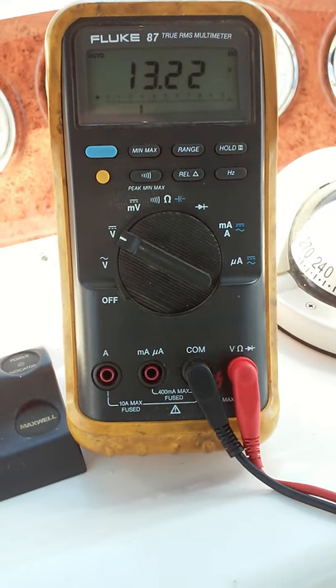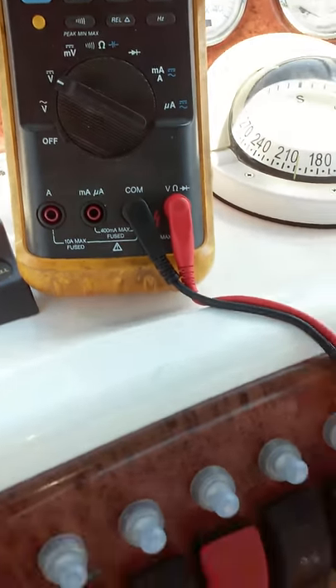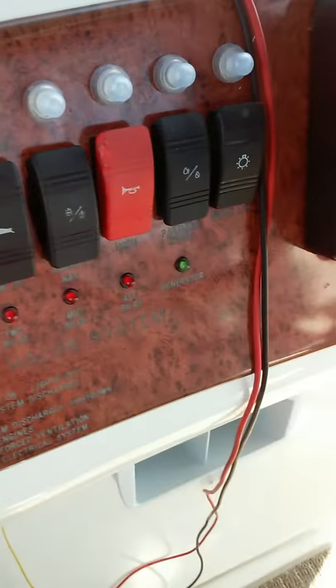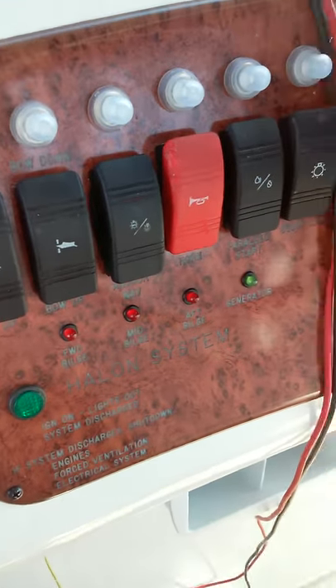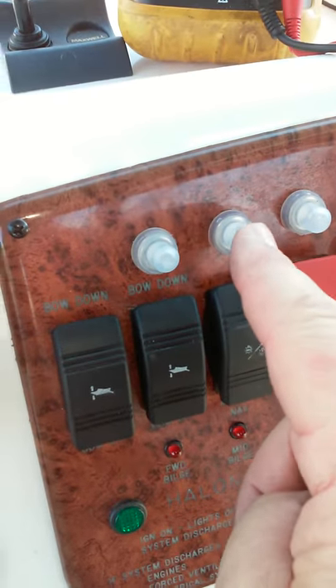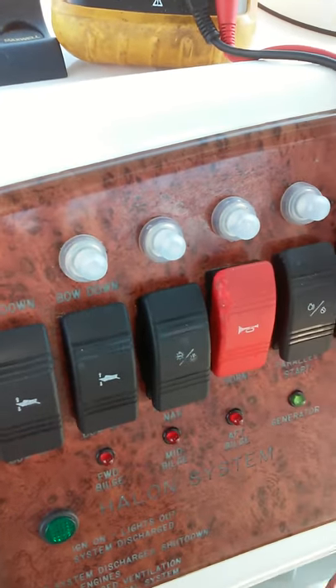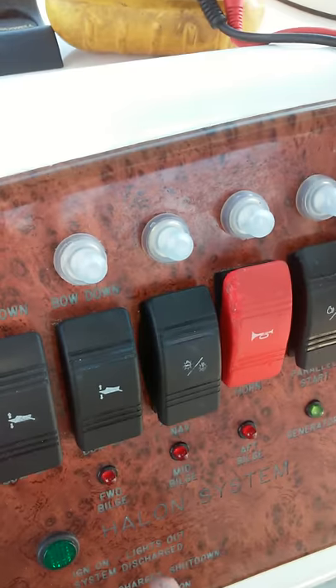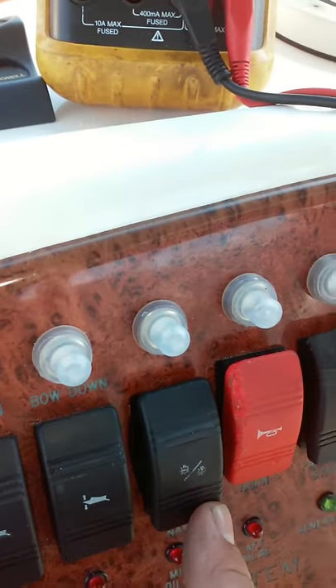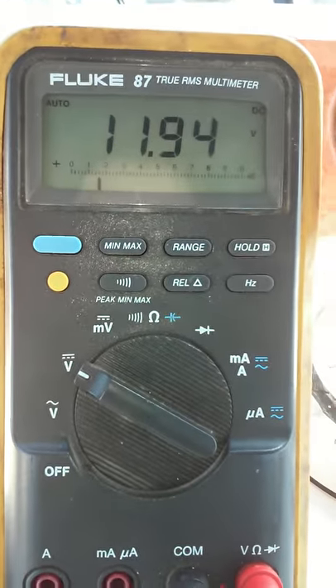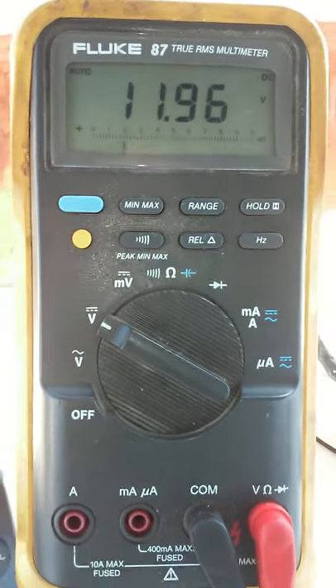So I hooked up a voltmeter to the power for the switch because it keeps throwing the breaker. It's a 15 amp breaker. So when I press the switch, I'm getting a significant voltage drop there.